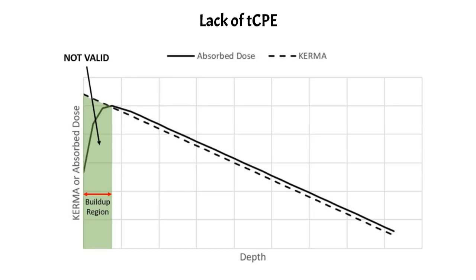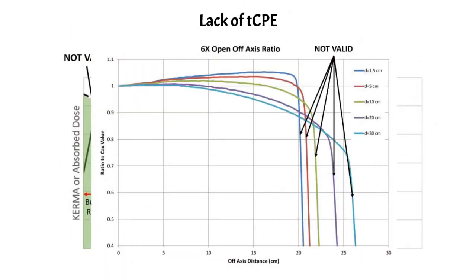The hand calc formalism is also not valid in the penumbra of fields. As shown in the profile diagram, the extreme dose falloff penumbra regions are invalid for the same reason as the buildup region — this is another region of charged particle disequilibrium, which is very hard to quantify with the detectors used to acquire beam data. Therefore it is very hard to predict what the penumbra will look like, and the hand calculation formalism is not valid there.